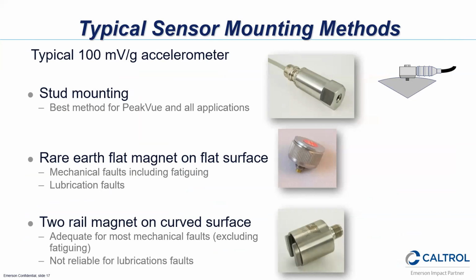And this is a different type of mounting that we use, the magnets that we use on the accelerometer. We use a flat magnet or a rail magnet to get onto the curvature of a motor or a bearing or whatnot. These seem to work the best. I'll show you in another video, but the accelerometer is attached to the analyzer the technician walks around with, and he uses a magnet on the end of the accelerometer and just moves from one point to another on a machine.